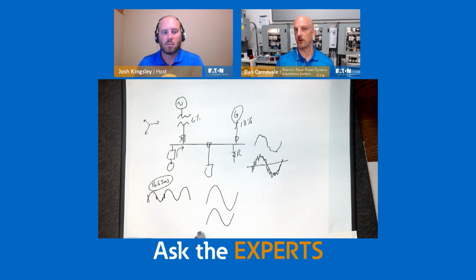So again, harmonic problems are a little bit difficult to track down after you have this issue, because it's not always just something overheats and burns up. It's something that over time heats and burns up, or this misoperation is a little bit intermittent. Sometimes it does it, sometimes it doesn't. So again, the things with the generators, and especially with voltage distortion that gets pretty bad, can be difficult to track down, but also it follows that simple rule of electricity, which is Ohm's law.